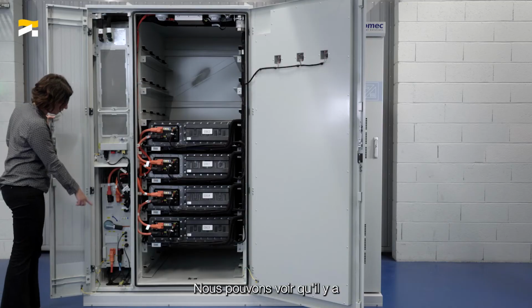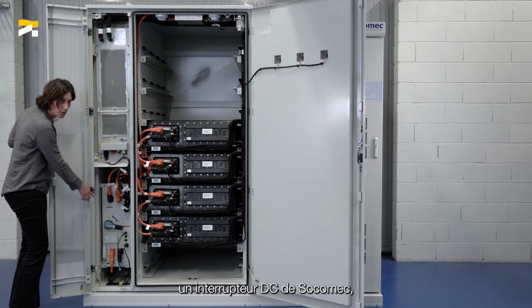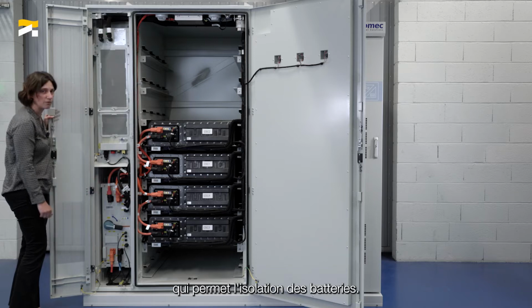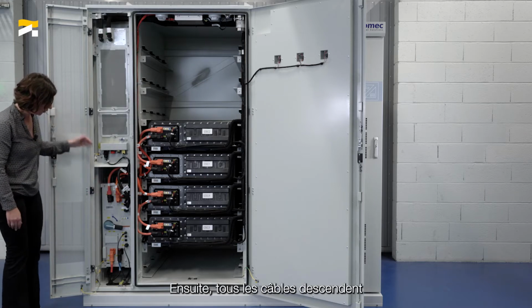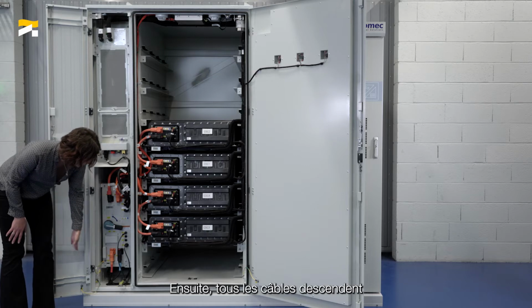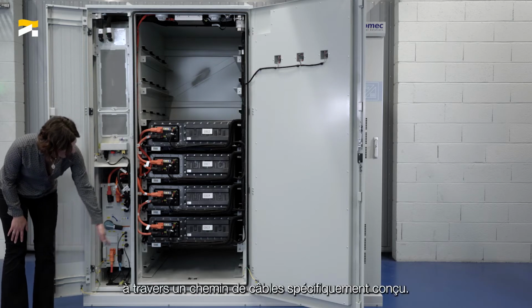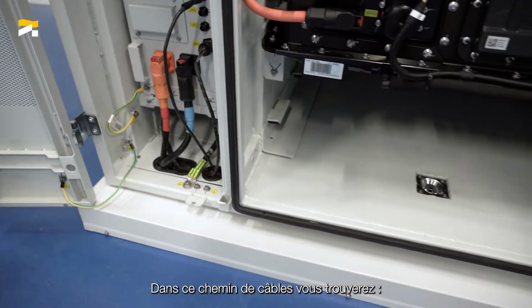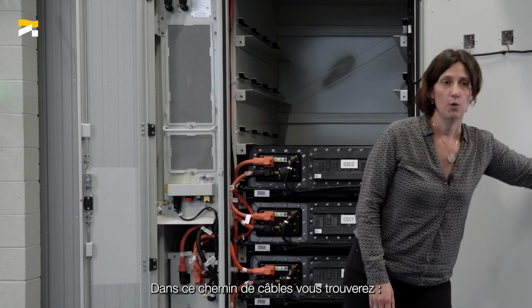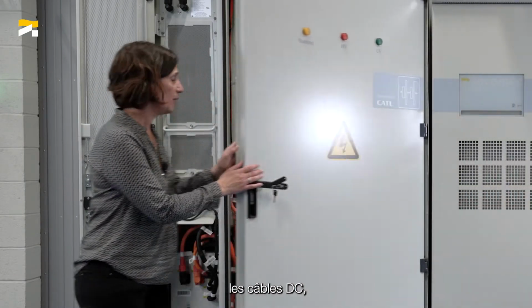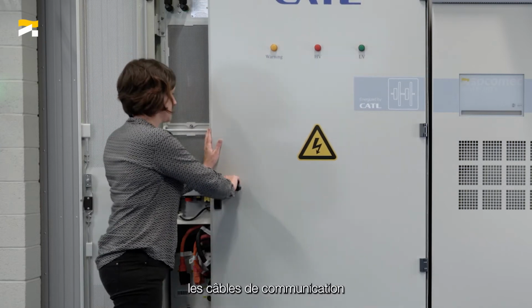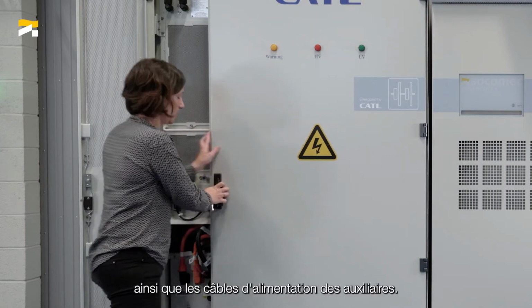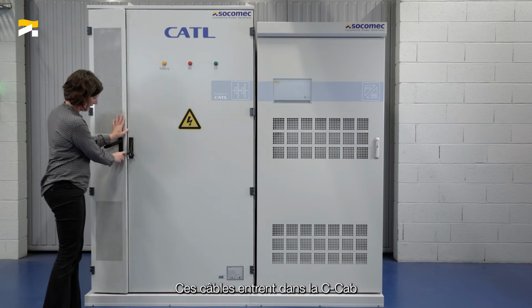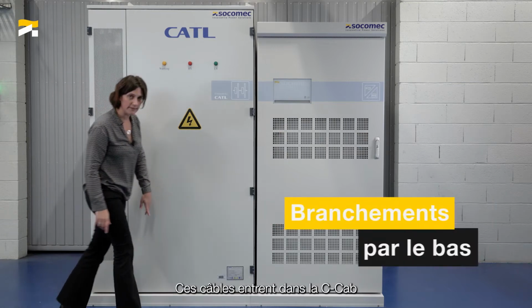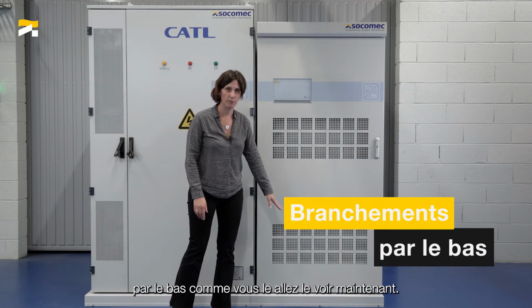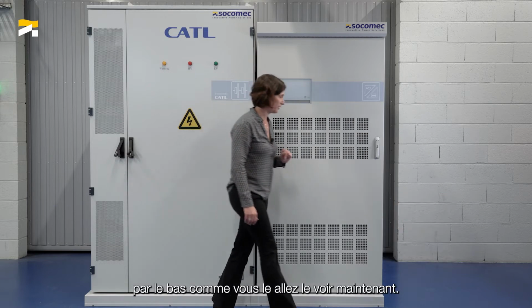So we can see that we have a DC load break switch, Socomec type, that enables to isolate the batteries. Then all the cables go down and go to the C-cab through a cable gutter that we designed. Inside this cable tray, you will find the DC cables, the communication cables, and also the auxiliary cables. These cables will then enter into the C-cab from the bottom part, as you will see right now.